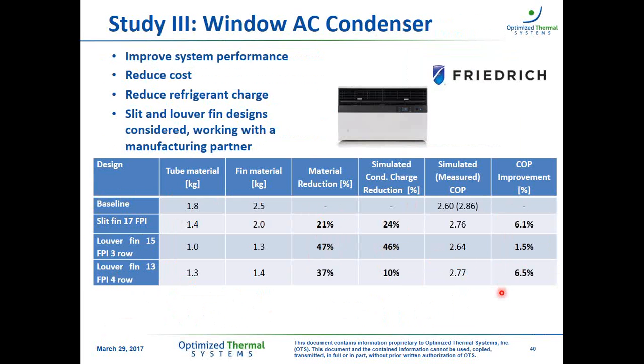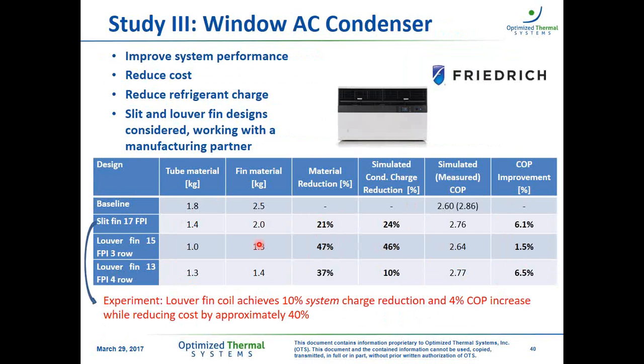Now, the interesting thing about this study is that for this particular heat exchanger, we have experimental data, and it ended up reducing the overall system charge by about 10%, while also increasing the COP by actually 4%, not the 6%, but still increasing the COP and reducing the cost by approximately 40%. So this is a pretty amazing improvement just by replacing the condenser with a small diameter tube design.